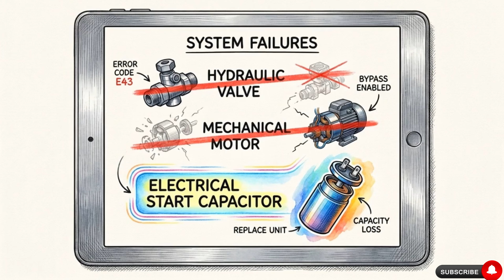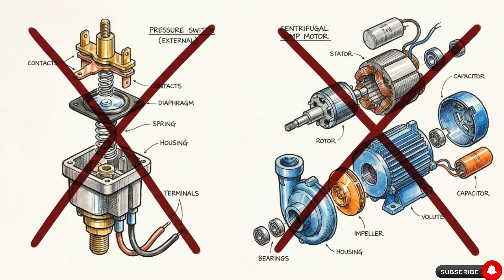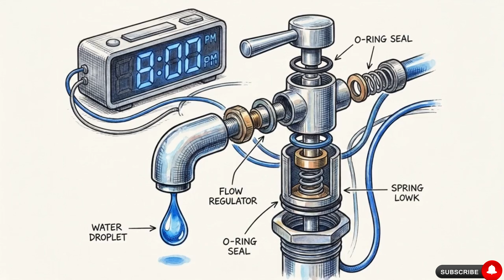Systematically eliminating alternative theories ensures the final diagnosis is driven by evidence rather than human conversational bias. Only now does the AI output a solution. The issue was never the pressure switch, and the motor wasn't dying. The pump had a degraded start capacitor, a small electrical component that had lost its charge-holding capacity. That's why it struggled to start in the evening, but ran fine once it finally kicked over.